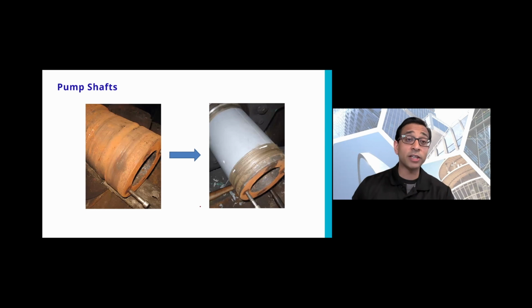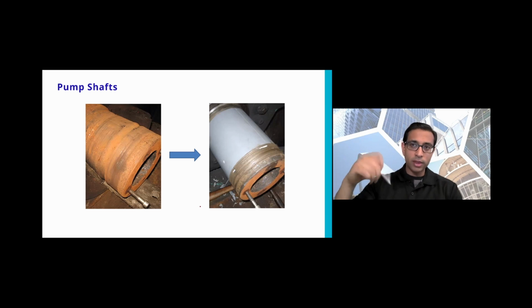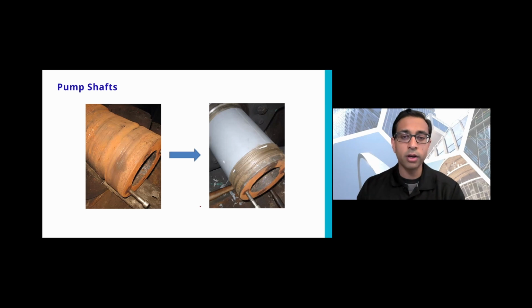Pump shaft. I just saw a really, really neat example. I was at a job walk, and in this case, it wasn't a pump shaft. It was actually an HVAC air handling shaft, and there was a motor at the end. This was about 15 foot wide, the air handler. But when we went in there and turned on the motor, it started shaking a lot, right? So the shaft was beat up really bad. They had to put a new collar on there. But you got to fix that shaft. If you don't fix both and there's not a snug fit, you're going to have a problem.